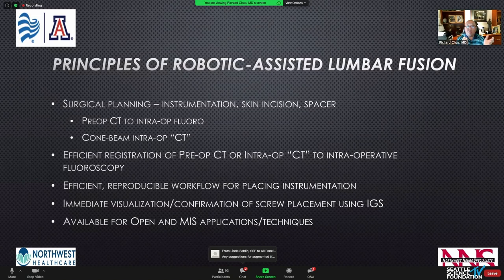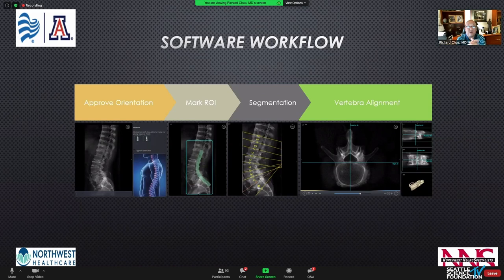The really elegant part is that software engineers have designed a registration software that merges two image sets so we can plan screws and let the robot execute them. It allows a very efficient and reproducible workflow of placing instruments, and we can potentially simplify and reduce steps because of the computerized planning and accuracy. The addition of image guidance allows immediate visualization and confirmation of screw placement. These systems are designed for both open and MIS techniques.